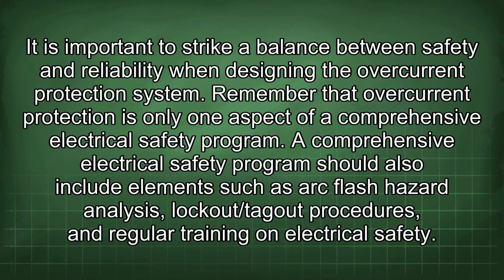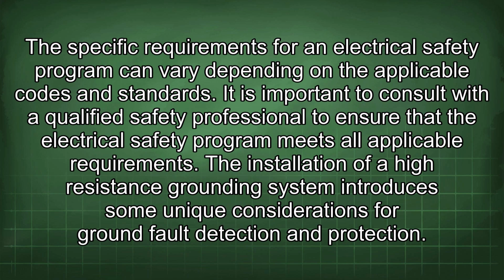A comprehensive electrical safety program should also include elements such as arc flash hazard analysis, lockout/tagout procedures, and regular training on electrical safety. The specific requirements for an electrical safety program can vary depending on the applicable codes and standards. It is important to consult with a qualified safety professional to ensure that the electrical safety program meets all applicable requirements. The installation of a high-resistance grounding system introduces some unique considerations for ground fault detection and protection.